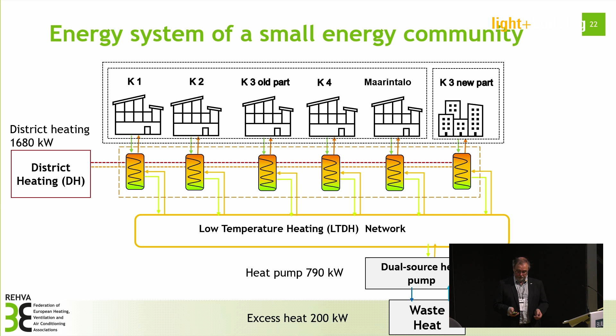So we have heat pump, excess heat, and then we have outdoor air. In this kind of system in the Finnish climate, it's challenging because from time to time it is quite cold. When the temperature is below minus 15 degrees, this heat pump does not use outdoor air as an energy source. It only uses the waste heat as the energy source because of the efficiency of the heat pump. That also means that, from a controllability point of view, it is a little bit more tricky in this climate.